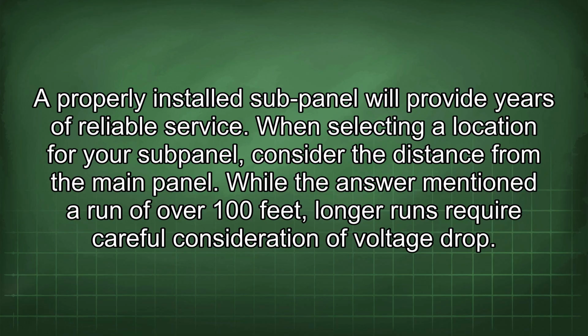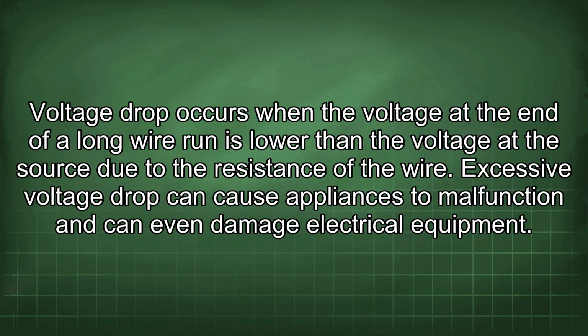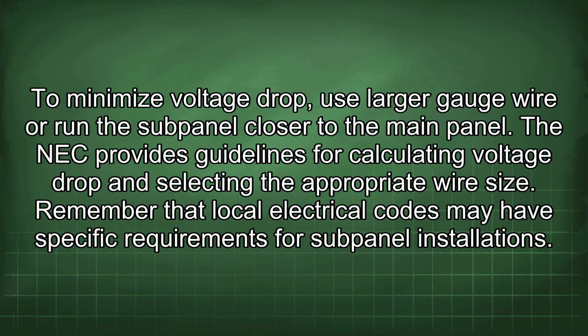When selecting a location for your sub-panel, consider the distance from the main panel. While the answer mentioned a run of over 100 feet, longer runs require careful consideration of voltage drop. Voltage drop occurs when the voltage at the end of a long wire run is lower than the voltage at the source due to the resistance of the wire. Excessive voltage drop can cause appliances to malfunction and can even damage electrical equipment. To minimize voltage drop, use larger gauge wire or run the sub-panel closer to the main panel. The NEC provides guidelines for calculating voltage drop and selecting the appropriate wire size.